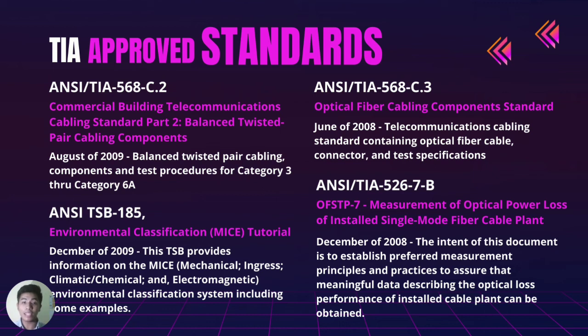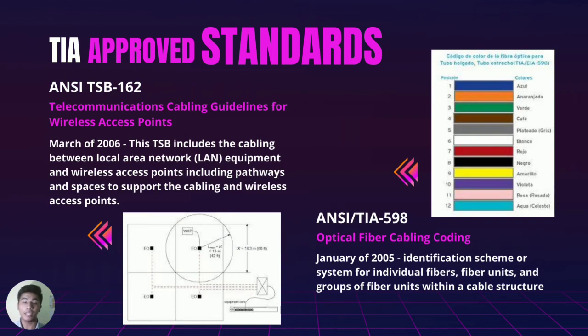We also have ANSI/TIA-526-7-B, or OFSTP-7, the measurement of optical power loss of installed single-mode fiber cable plant. It was approved last December of 2008. The intent of this document is to establish preferred measurement principles and practices to assure that meaningful data describing the optical loss performance of installed cable plant can be obtained.